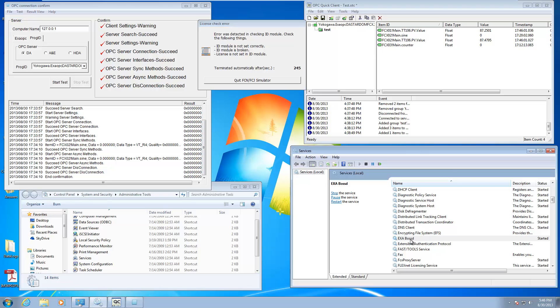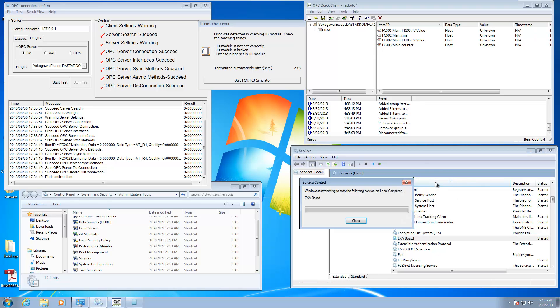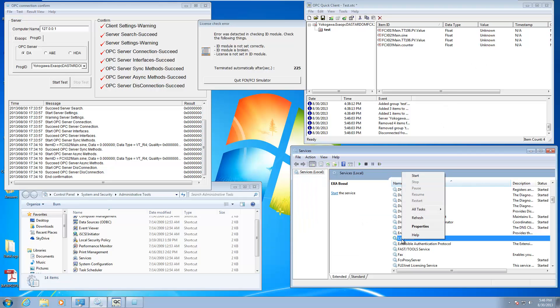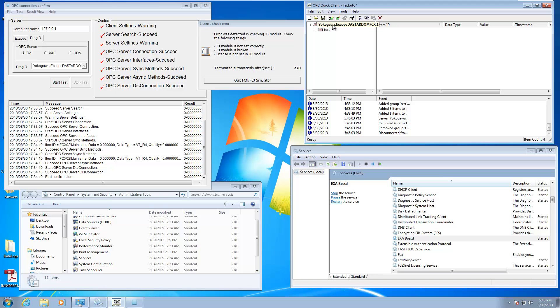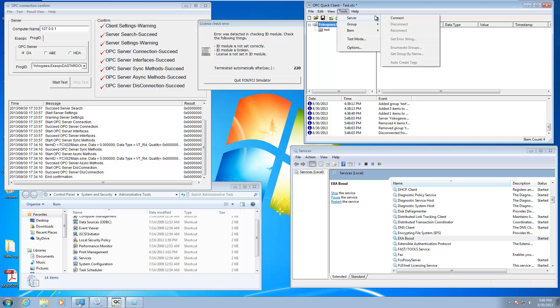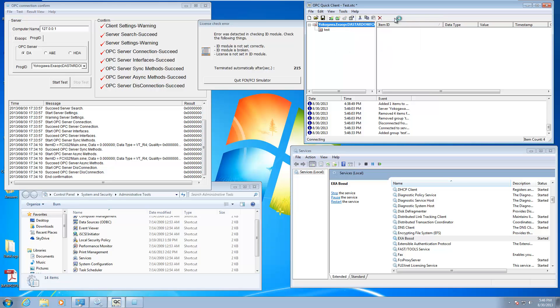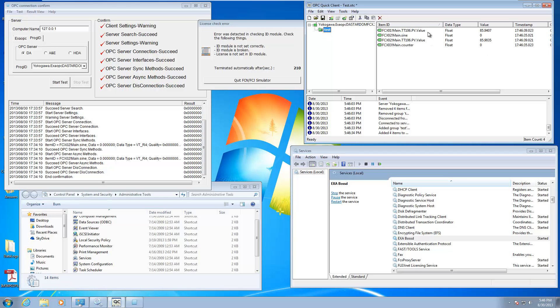Let me show you what that's going to look like. So I'm going to stop it. If you noticed up here, my OPC quick client, everything immediately went offline. So yes, if you have any SCADA packages attached to it or OPC clients attached to it, you're going to lose the connection. So just be aware of that. But at least it's saving you a reboot. And then I can go ahead and start here. Now that I'm started back up, if I got an OPC system, I can just go ahead and do a connect to the server and you can see everything's back and running again. So I kind of reconnected. And you can see I've got a few different values coming into the OPC quick client.